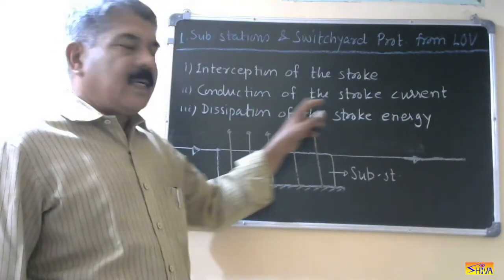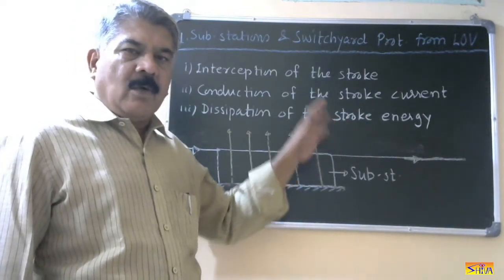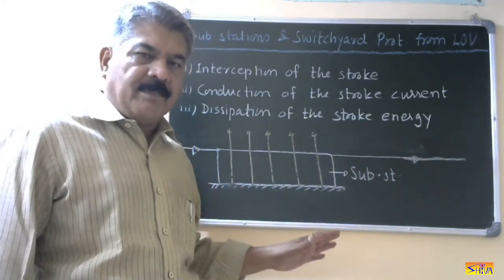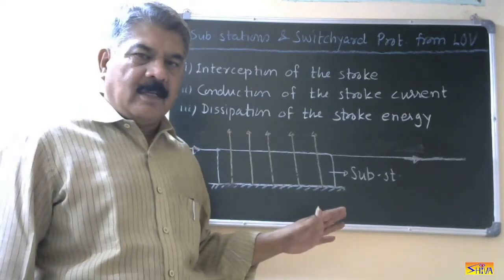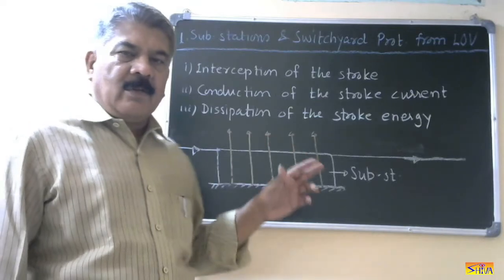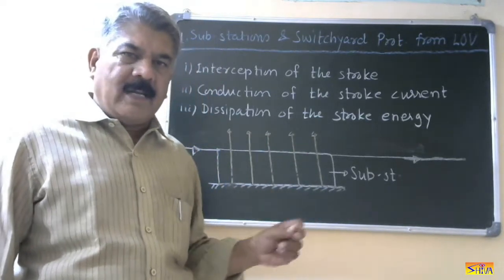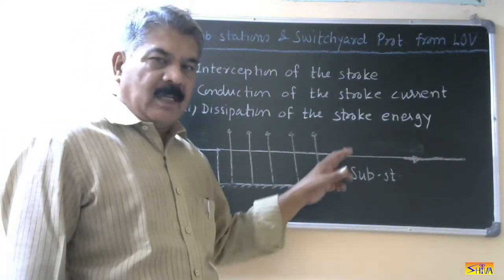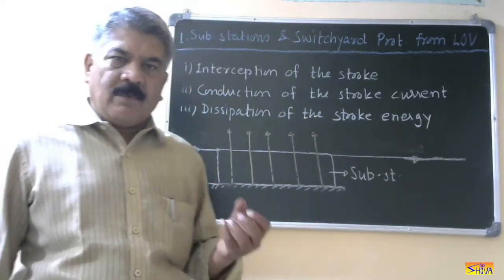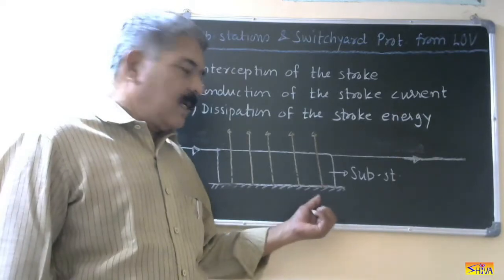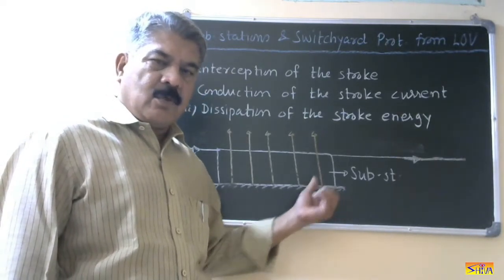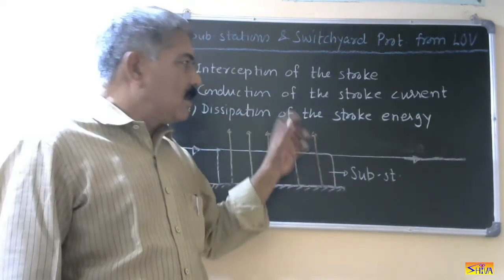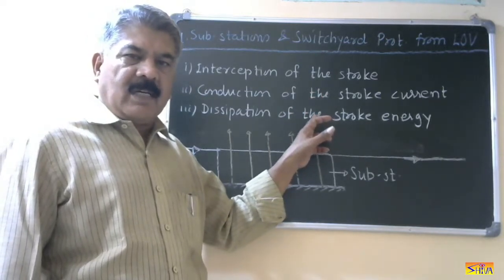The second step is conduction of the stroke current. Whatever discharge current flows must flow through that object only and not through any other object. Therefore, these metallic objects or electrostatic shielding must have minimum resistance so that the stroke current prefers this path only. The third step is dissipation of the stroke energy. Since this current is very high, we require resistance to dissipate that energy so that nothing unwanted happens.